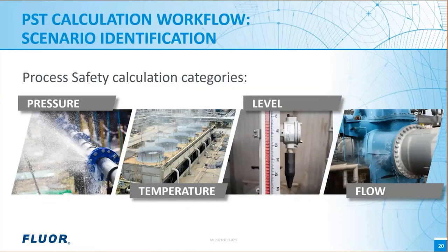As another example, in level, you might have a flare knockout drum, and it's tempting to say that on a high level trip, your point of failure would be the point where the drum is full to the brim. And I think that the problem with that is that obviously you may experience liquid carryover with that flare knockout drum long before the drum is full, and that might lead to fire rain from the flare. Or similarly, if the drum is a compressor suction knockout drum, there may be liquid carryover into your compressor long before the drum is completely full. So my point here is to think carefully about the scenario and point of failure, as it may not always be completely obvious.